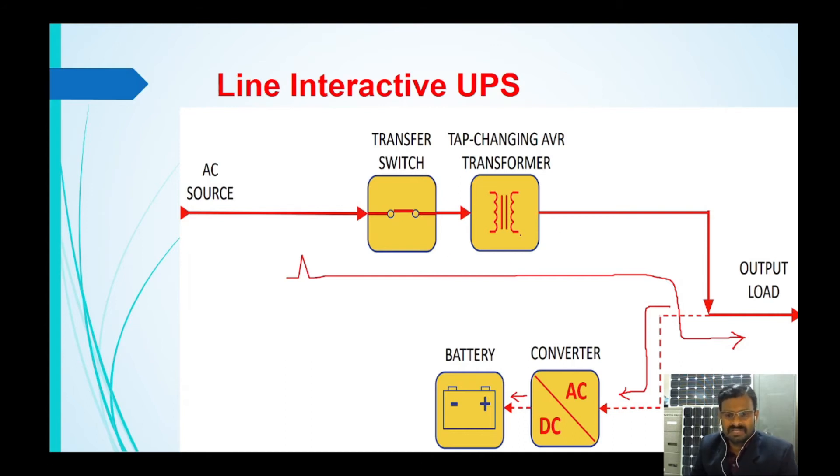What is the role of this tap changing AVR transformer during this mode? Whatever voltage fluctuations coming from the input, since it is a tap changing transformer, the taps can be changed in accordance with the AC input. If it is high voltage the tap can be reduced, or if it is low voltage the tap can be increased, so that the output voltage to the load will be maintained constant.